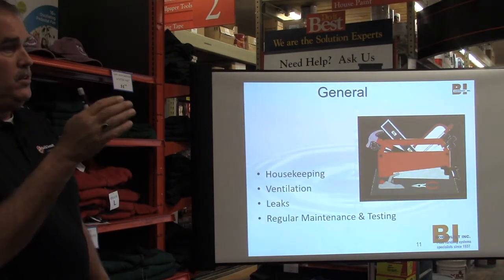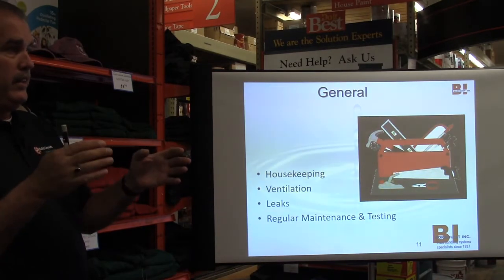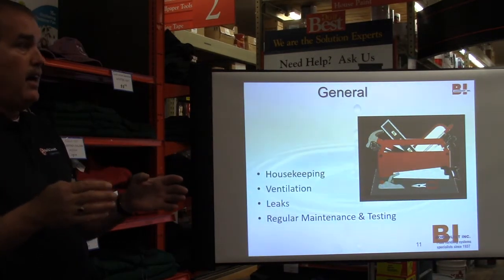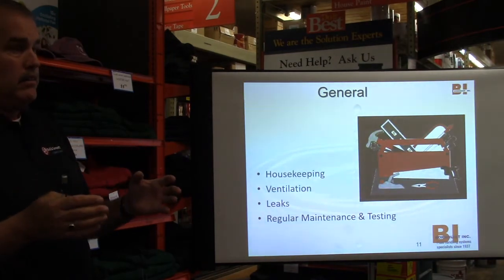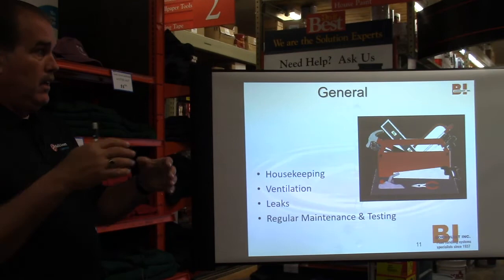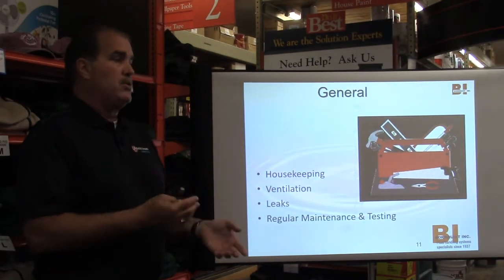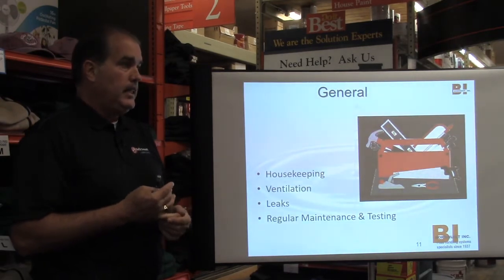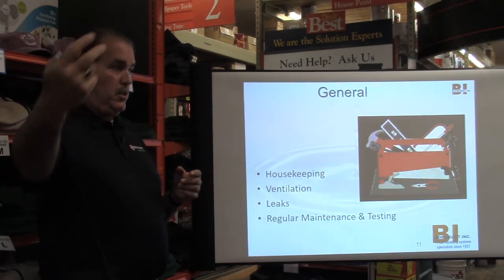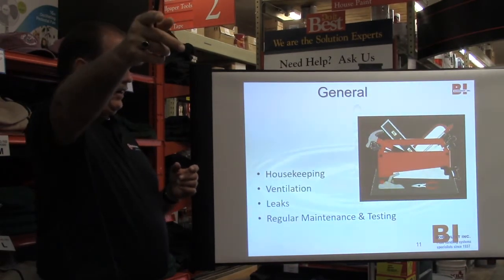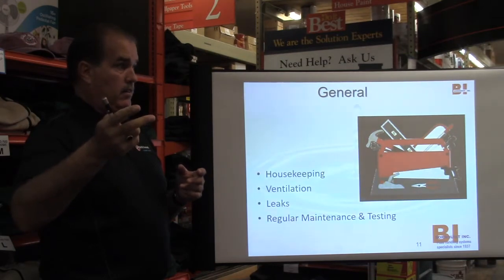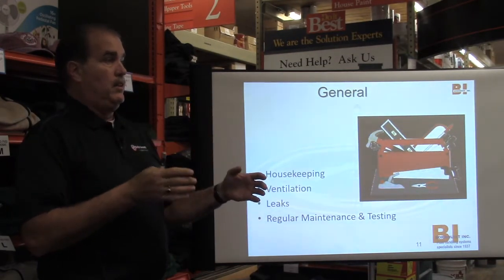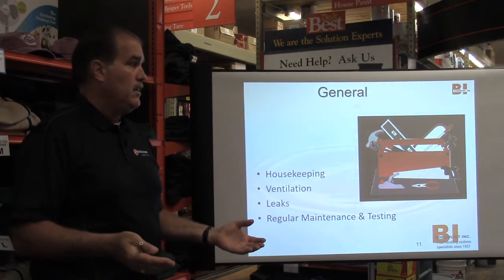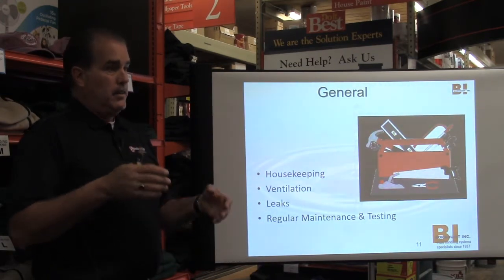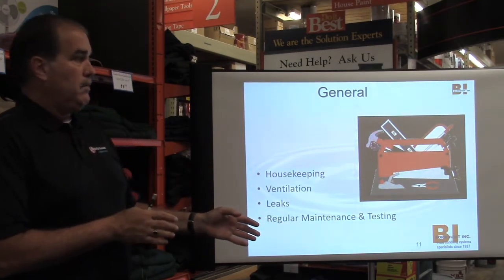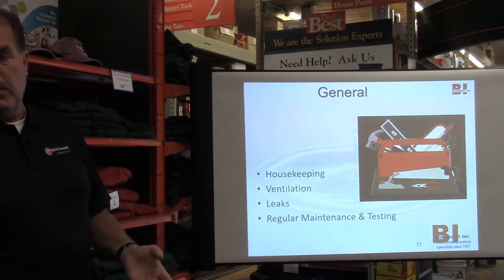Ventilation. If you have a boiler or water heater in a closet, which is not uncommon, it needs air. It shouldn't be in a sealed up closet, because that's the absolute worst thing in the world for any gas-fired appliance. They need air unless it's sealed combustion, which means it's pulling the air from outside and then dumping the flue gas back outside, so it has a means of giving itself its air. If you do not have that, the doors need to be louvered because you're pulling air from the inside of the house in order to fire that. So, as much as people want to hide their heating equipment so that no one sees it, you need to let it breathe. It needs the air.